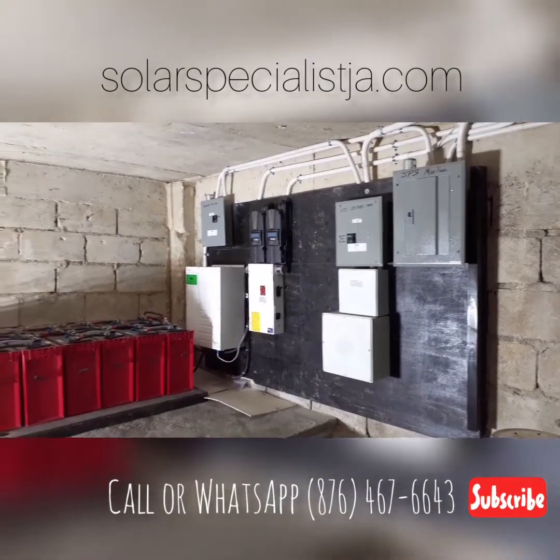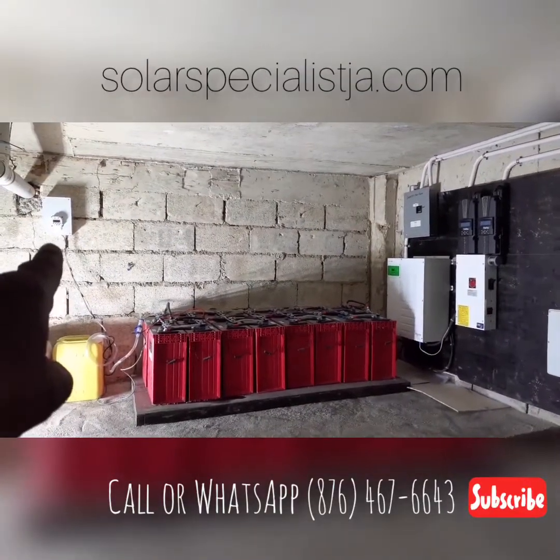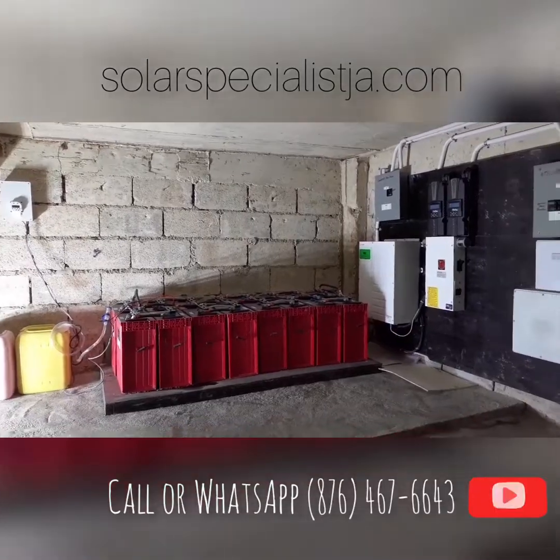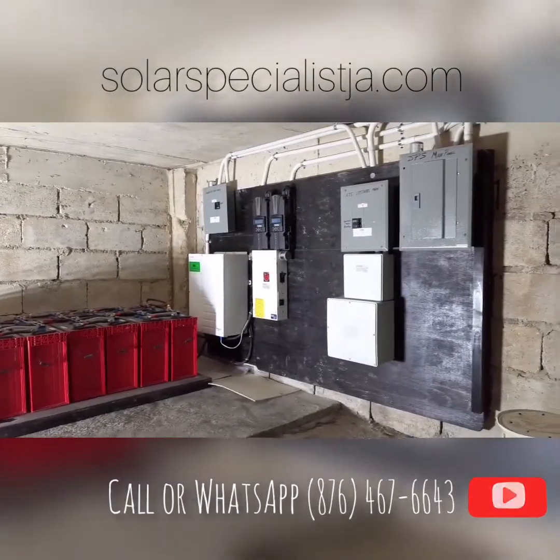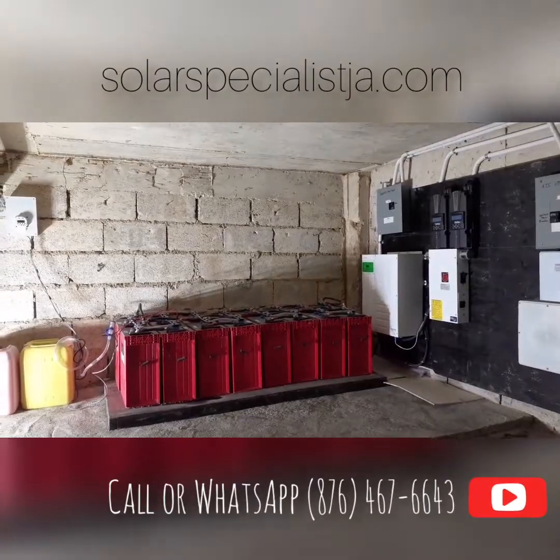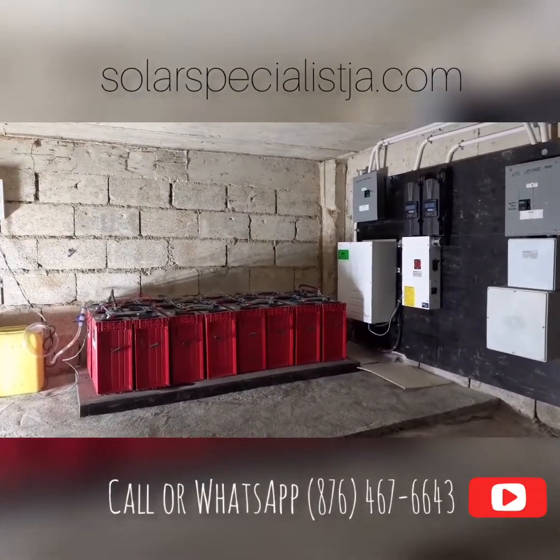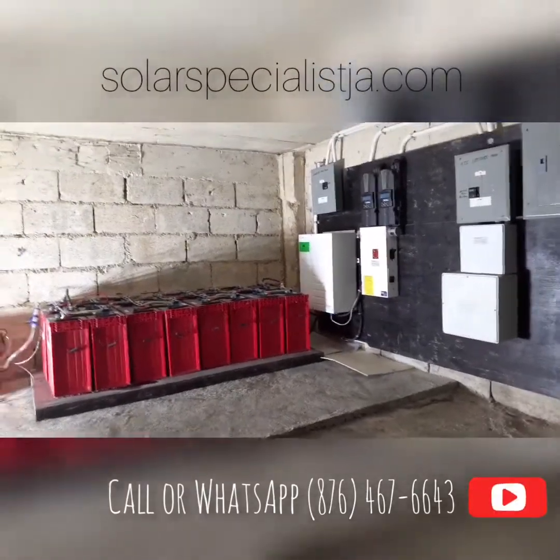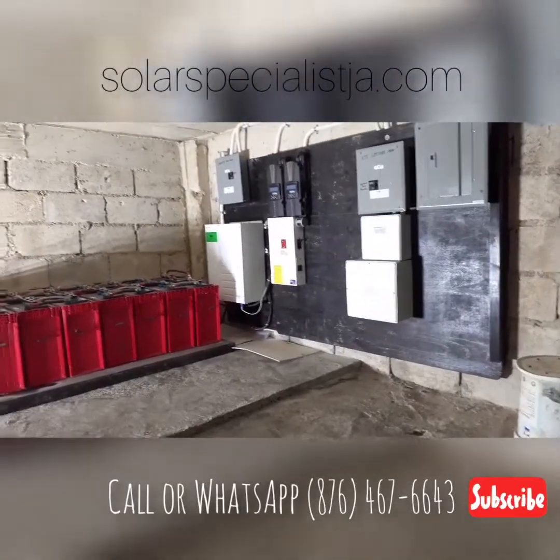There we have it — the finished product. We have a timer for the battery watering system on these Rolls S6 L16 445 ampere-hour batteries. With 16 batteries we have approximately 20 kilowatt hours of storage, and we'll be adding another eight batteries for a total of 30 kilowatt hours of storage. Our 24 panels will produce approximately 30 kilowatt hours on a bright sunny day once the batteries are drained and able to take the charge, giving us a total of around 25 to 30 kilowatt hours of usable storage.